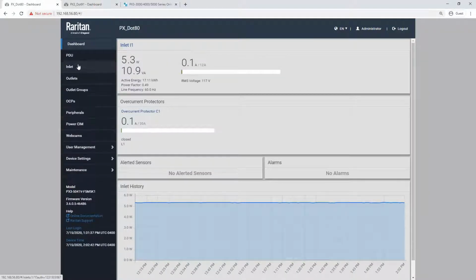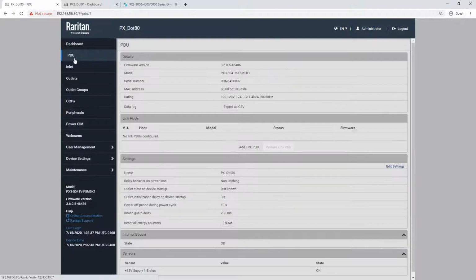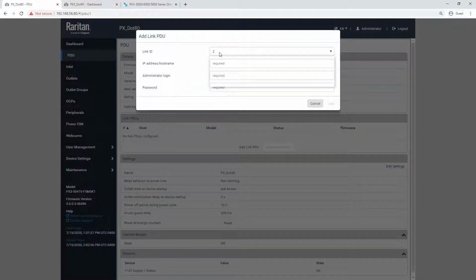So we're going to jump into the PDU menu of the one that we want to be the primary PDU. You'll see in the second section of the PDU menus is 'link PDUs'. I can click this button and select a link ID for my link unit, so it should be a number 2 through 8. The primary PDU automatically receives a link ID of 1 - you can't change that - but you can change the link ID of the link units based on its position in the chain or however you wish to identify that particular PDU.